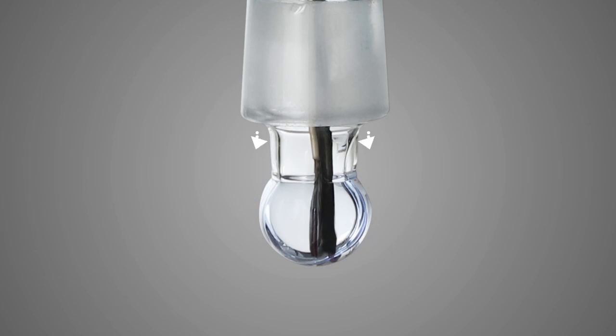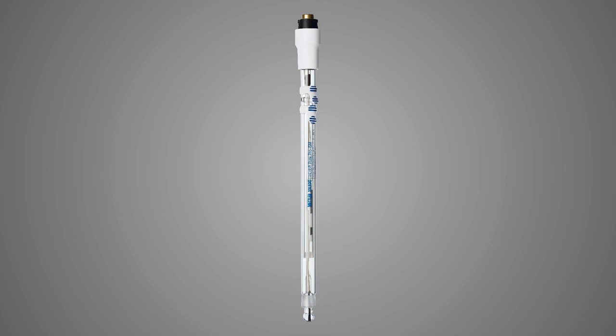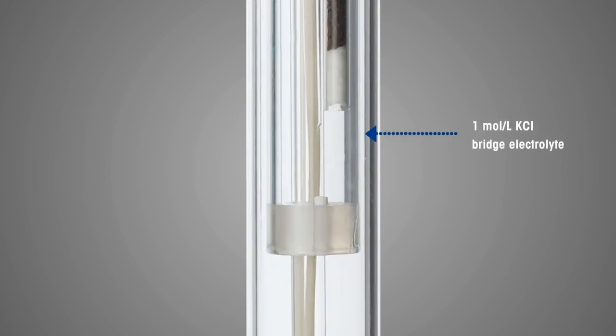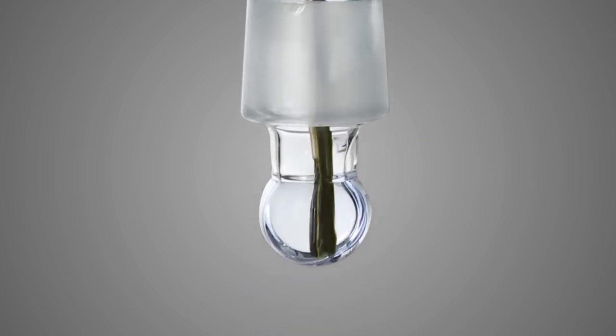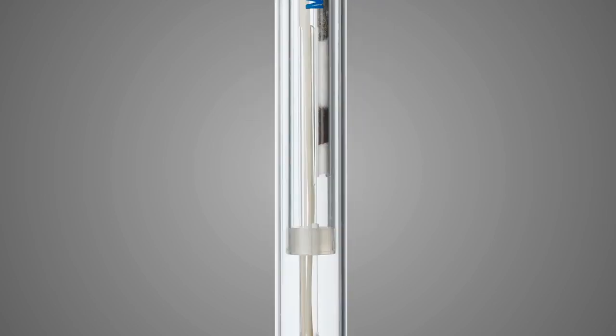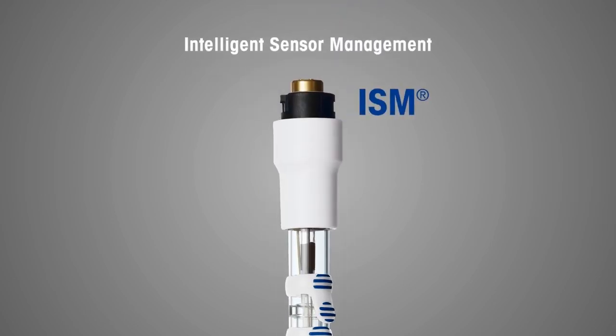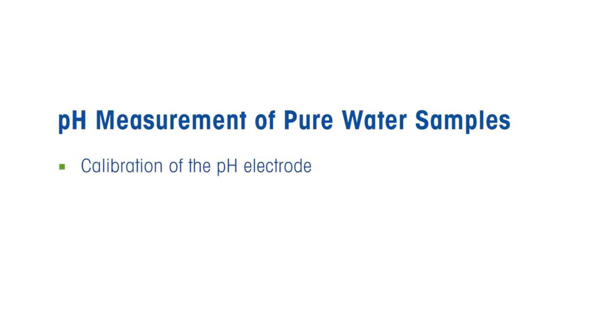The sensor has a glass sleeve that allows a steady outflow of the electrolyte. 1 molar instead of 3 molar potassium chloride electrolyte is used to reduce liquid junction potential and ensure highly accurate pH measurement. This sensor has an inbuilt temperature probe. Thanks to the intelligent sensor management, the electrode's name, serial number, and calibration data are stored in the sensor itself. Now we will see the calibration of the pH electrode and pH measurement in deionized water.